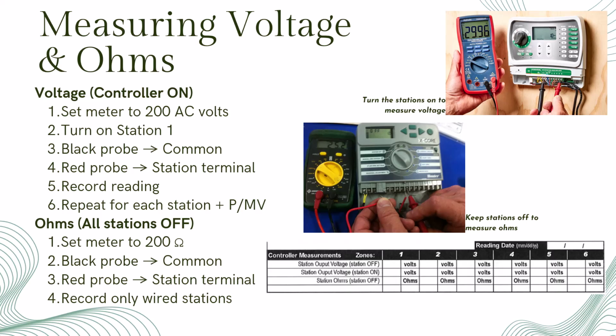Measuring voltage and ohms is a standard part of spring startup or yearly maintenance on a controller. These readings give us a baseline for each station, so when a problem shows up later, like a weak solenoid, damaged wire, or failing relay, we can spot the change before the system fails. It's really about prevention, not reaction. By measuring and recording these numbers on the irrigation service checklist, we create a reference that helps diagnose future issues quickly and accurately.